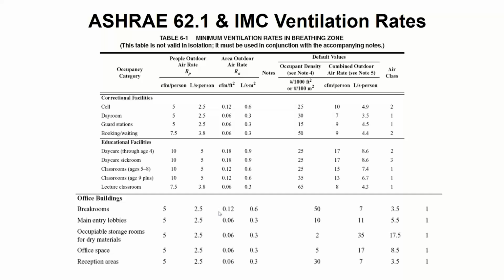Well, obviously, if I take my airflow on my fan and cut it in half, but my outside air intake opening stays the same, I'm going to cut my outside air in half as well. The code doesn't allow me to do that. The code says you've got to ramp the outside air up. So as I throttle the fan down to a lower speed, I have to increase the damper opening, so I always get, in my example, the 1,100 CFM of outside air.